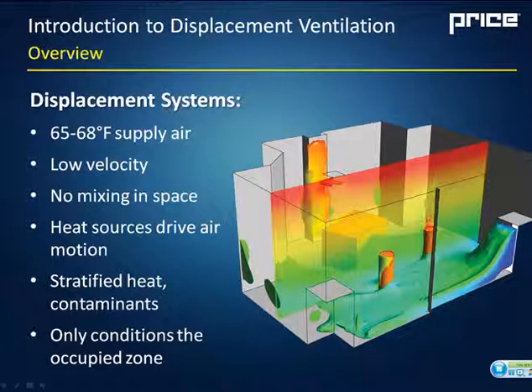Now contrasting that is a displacement system where we have much warmer supply temperature, where we had 55 degrees with the mixed system. We have 65 to 68 degrees or even up to neutral to room temperature supply. And very low velocity. In this case, it's usually around 40 to 50 feet per minute from the diffuser face. So you see in the lower right-hand corner here, this is the diffuser. And the air is just spilling out of the diffuser. It's then traveling across the floor, and it's pulled towards the heat sources. So in this case, there's very little or no mixing in the space, and the heat sources are driving the air motion.